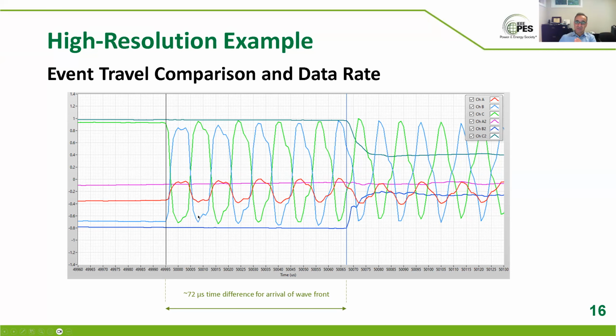If it's 8.2, that means the time to travel from the fault to the terminal and back is 8.2. So the distance is 4.1, half of that. And 4.1 times 300 meters, the fault is at 1,230 meters, right? So you get to 1.23, not just 1.2. You get an order of magnitude better resolution. In this case it's not within 300 meters, it's within 30 meters, you're confident where the fault is. This is a special case, but when you see these patterns, you can take that sort of information out of it. This is purely an example of accurate fault location, right?